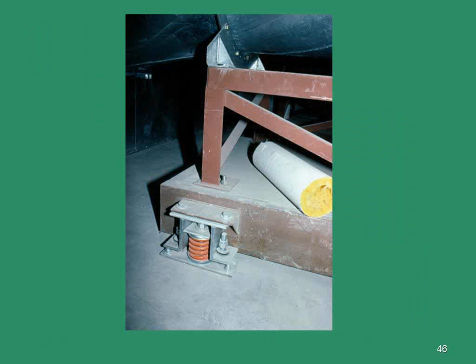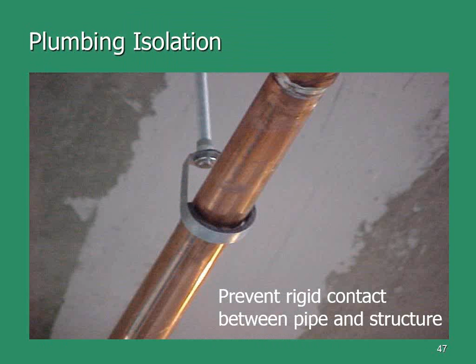So I got on a plane and flew down there, and we're going to zoom in a little bit. What happened, in retrospect, was almost comical, but it wasn't very funny at the time. When they put these springs in, they jack up the whole inertia base of the fan using big 1.5-inch diameter nuts to support it while they slide the springs in and bolt them, then they're supposed to let them off and level them. Well, what you can't see in this picture is, if you got down and shone a light up under it, it was still sitting on those four hard points of contact, not actually riding on the springs.